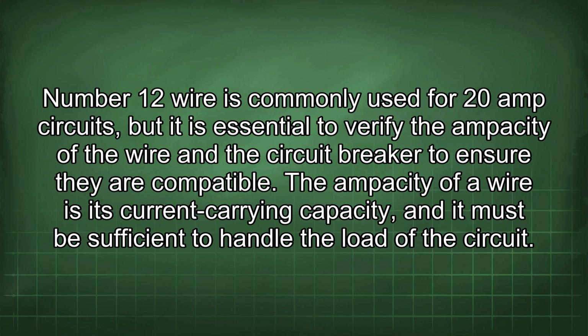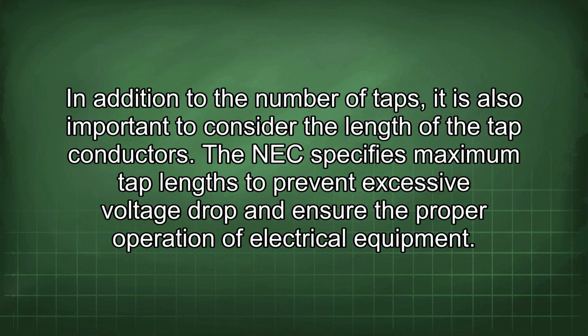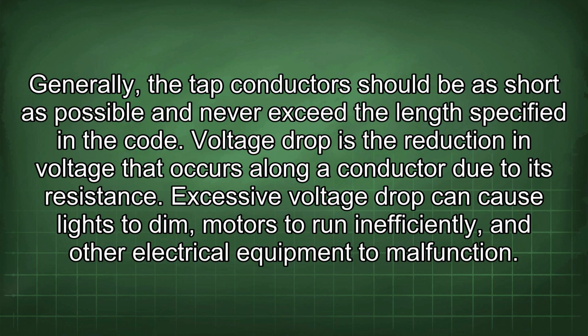The ampacity of a wire is its current carrying capacity, and it must be sufficient to handle the load of the circuit. In addition to the number of taps, it is also important to consider the length of the tap conductors. The NEC specifies maximum tap lengths to prevent excessive voltage drop and ensure the proper operation of electrical equipment. Generally, the tap conductors should be as short as possible and never exceed the length specified in the code.